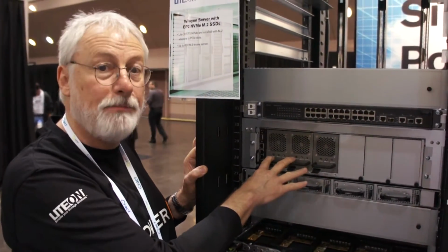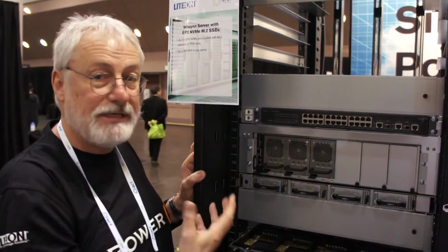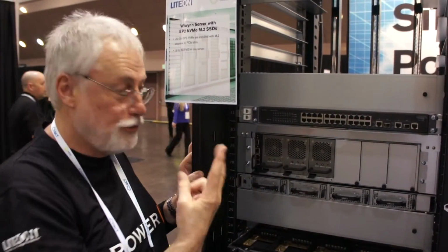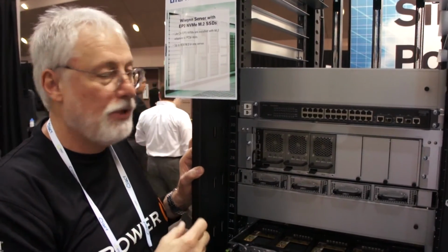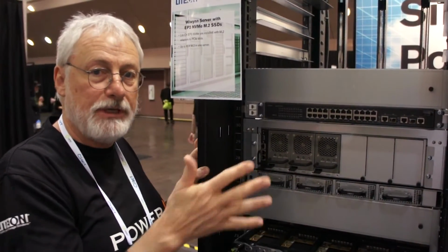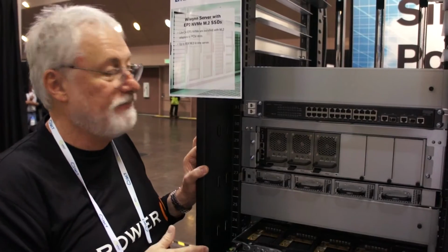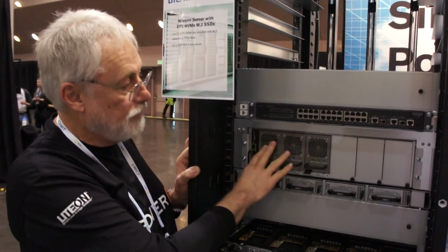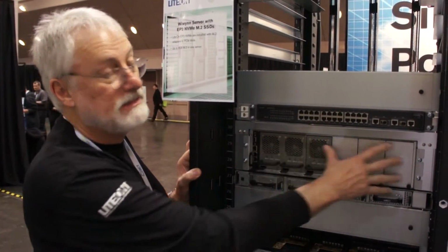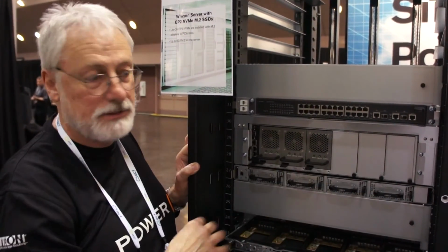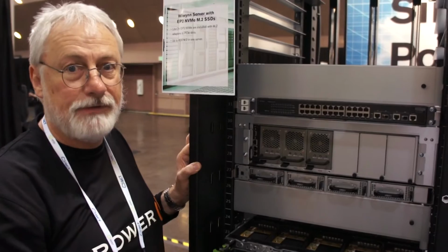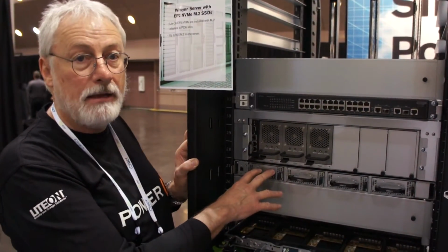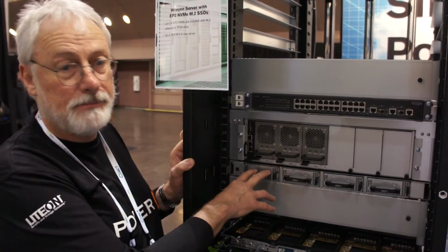And this is a dual input capability, so you can bring a redundant feed in, and each power supply has the ability to take in two AC inputs and then automatically switch between whichever one is available. So this gives you a redundant feed capability at the power supply level. 2.5 kilowatts per power supply, 6 slots, so on a 5+1 redundant configuration with 12.5 kilowatts. You can also add a battery backup capability.